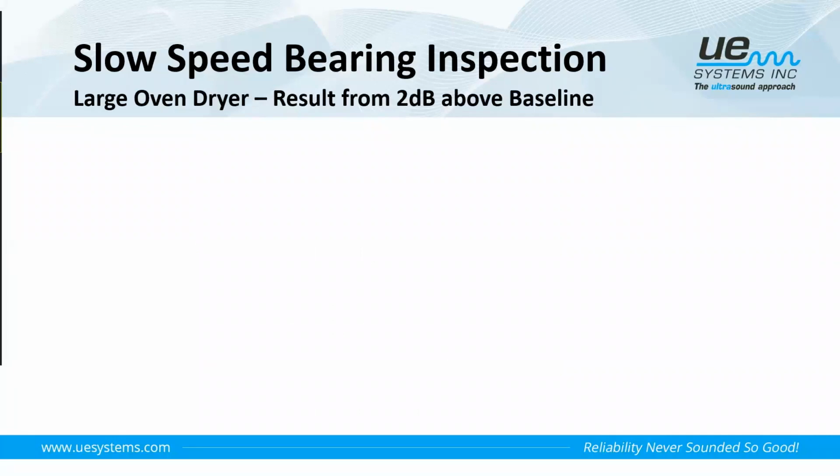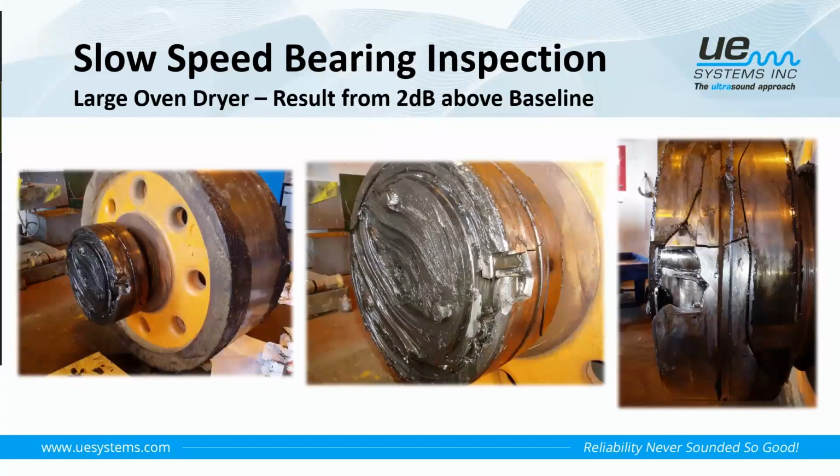So the site decided to remove this bearing, or schedule the replacement of this bearing. After they took it out of situ, they sent me pictures of the damaged bearing. As you can see from the images, there were some severe cracks. Part of the outer race fell off, the cage inside had damaged, and one of the rolling elements had moved 90 degrees. So this was a great find, a good way of identifying a problem at an early stage. It would have failed dramatically at some point, but we caught it early enough to get the work done in a scheduled way.